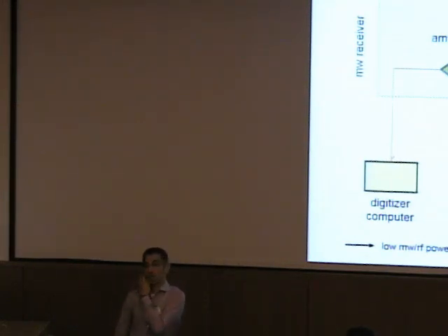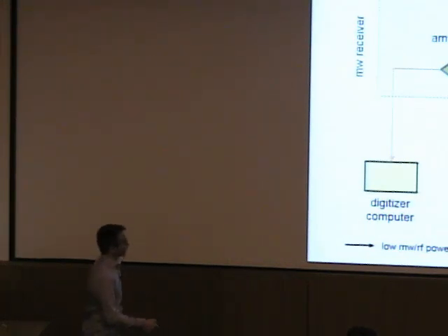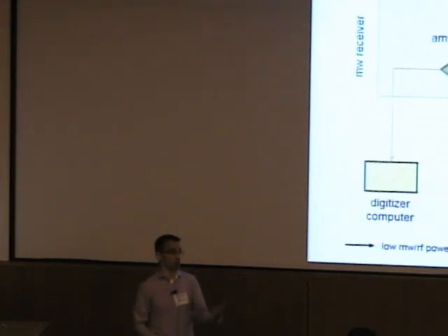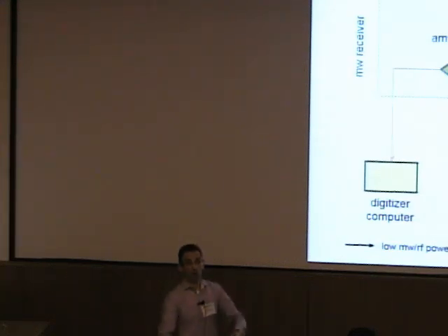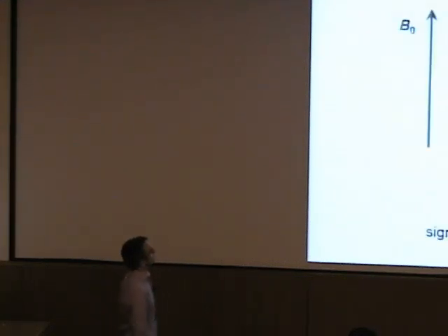Sometimes we're also doing NMR at the same time. So we're not just hitting the electron spins, but we're also hitting the magnetic nuclei. For example, we could do proton NMR at the same time. So we have a built-in NMR transmitter in the Pulse EPR spectrometers. And this method where we do both at the same time is called ENDOR, for electron nuclear double resonance. It's kind of a combination of NMR and EPR. So that's how Pulse EPR works.